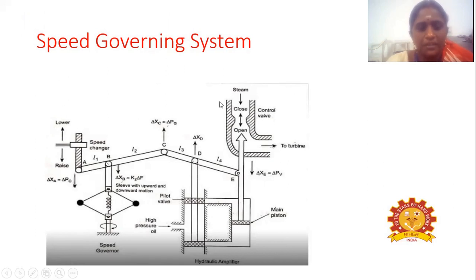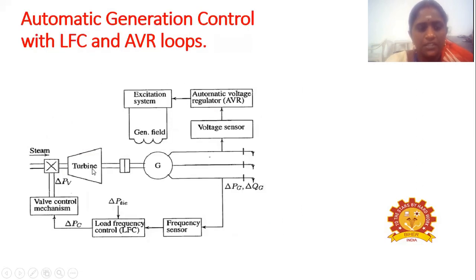So here there are many blocks: speed changer, then speed governor, then hydraulic amplifier, and then steam control valve, like that. If you want to increase the speed, when the frequency is very low, we have to increase the speed. Then we have to allow more steam into the turbine.